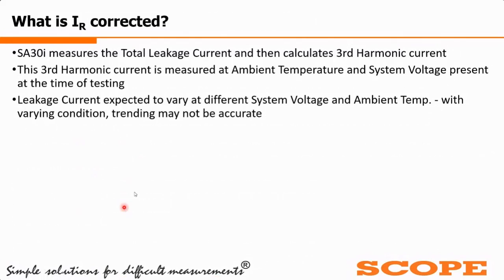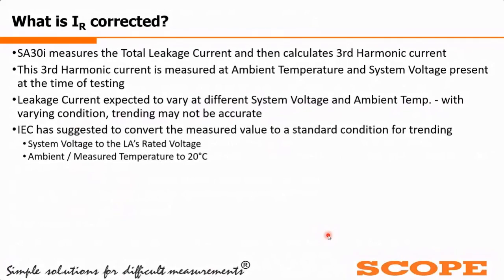So leakage current is expected to vary at different system voltage and ambient temperature. With varying conditions, trending may not be accurate. So I must refer to a standard value. IEC has suggested how to do this standardization. They have suggested converting the measured value to a standard condition for trending. For doing the trending, we have to take the reference of system voltage, the LA's rated voltage, and convert the measured temperature to a standard temperature of 20 degrees centigrade.